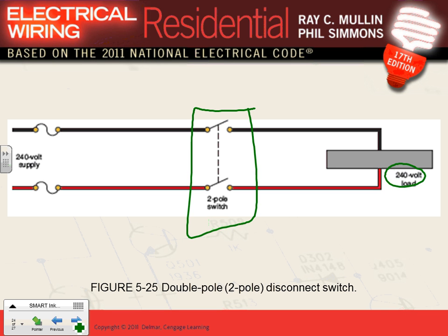In a commercial building, if you want to burn ballasted equipment at say 480, you can burn them at 480, or you can burn them at 240. Then this snap switch has to be 2-pole. Typically, they don't use them a lot because they use other lighting control systems, and you can also use the circuit breakers as switches. So sometimes it's 240 volt delta, to burn the lights at 240.